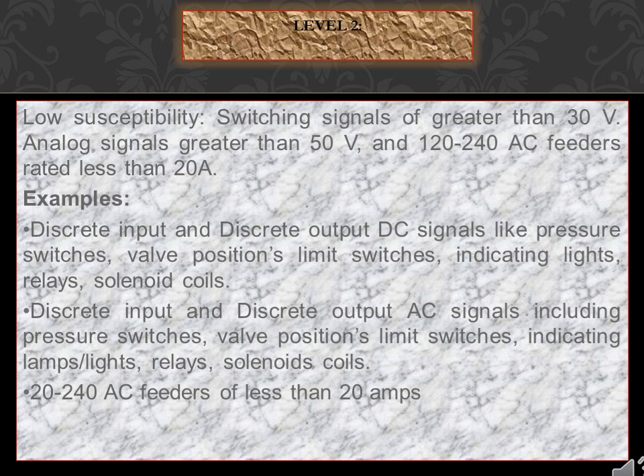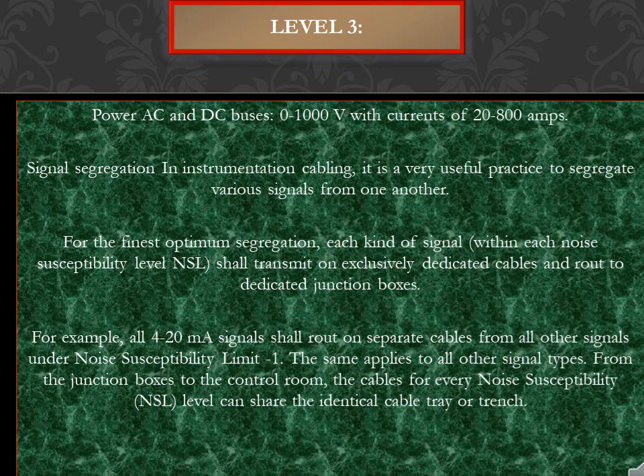Level 2 also includes 120 to 240V AC feeders rated less than 20A. Examples include discrete input and output DC signals such as pressure switches, valve positions, limit switches, indicating lights, relays, and solenoid coils, as well as discrete input and output AC signals including 120 to 240V AC feeders of less than 20 amps.